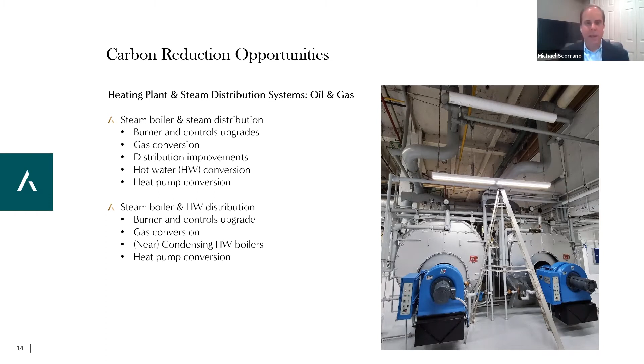Steam boilers and steam distribution are very common, especially in older buildings, and even some newer ones built just a couple of years ago still use steam distribution. But there are ways to upgrade it: changing burners, upgrading controls to be more modern, and looking at distribution system measures like steam traps, two-pipe versus single-pipe systems, and venting opportunities to get steam to locations better. There's definitely a lot of opportunity there.